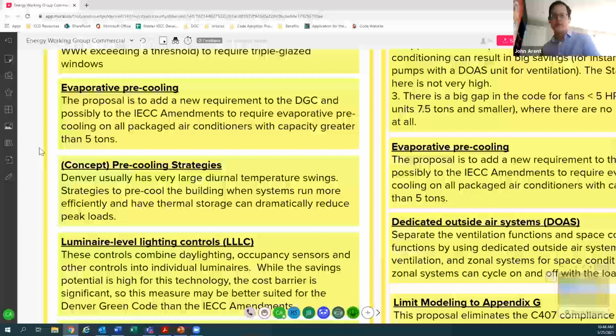There's a building in the Bay Area where they've used some of these strategies to some extent. As opposed to pre-cooling, it's a small or medium-sized office building, and they run the cooling tower at night when it's efficient, then store chilled water for use during the day to offset some of the cooling load.